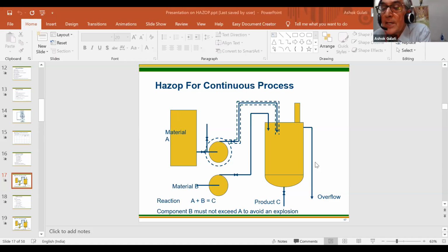Okay. A proper control mechanism, Shri Krishna, now this is not very clear. Flow can be 0, a proper control mechanism. What is a control mechanism? If you're talking about only the isolation valve, yes, supposing somebody was to operate the isolation valve and the isolation valve is shut, then flow can be 0. That is true. Material A is finished in the tank is also a very right reason. It was working normally and the level in tank A was reducing, and a stage comes where it loses priming because the level goes below the suction point.